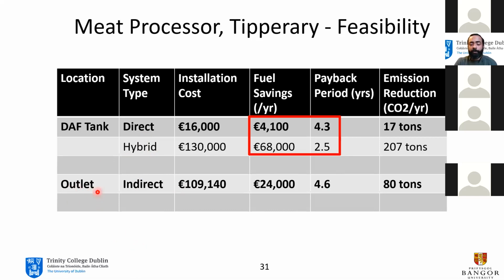And even at the outlet, where the temperature was quite a bit lower, as you guys saw, it was still quite good for the payback period, at 4.6 years. So there's less heat, so there's less cost offset overall every year. But the installation costs are a bit lower because you don't have to have both heat exchanger and a heat pump there. We could just use a heat pump directly because the water is cleaner.